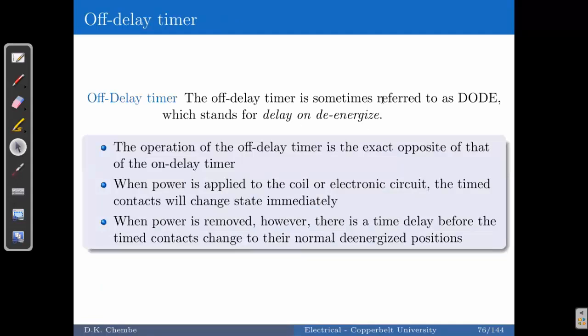The off-delay timer is referred to as DODE — delay on de-energize. This implies it begins its timing delay after it has been switched off. The operation of the off-delay timer is exactly opposite to that of the on-delay timer. When power is applied, the timed contacts will change their state immediately. But when power is switched off, that is when the timing action begins.